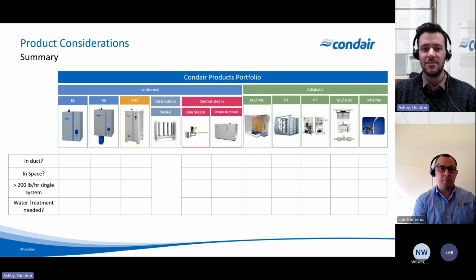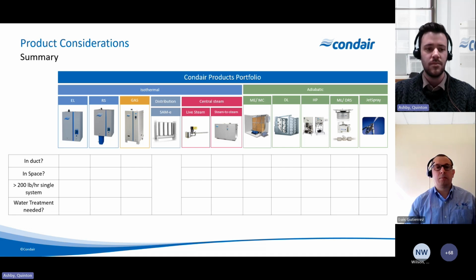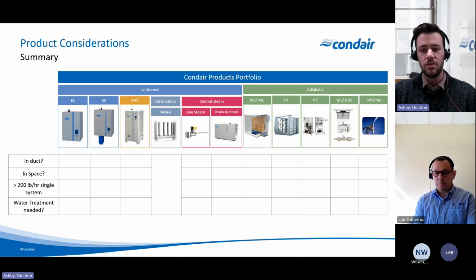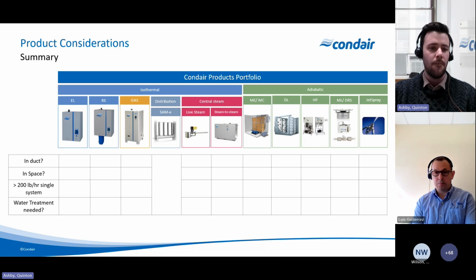So a little bit more specialized for the specific application, but then again, adiabatic does cover the full range. Another thing that we would want to look at too is the size of the system. That's a good first step if you're looking at a new job. And we think around 200 to 250 pounds is kind of the turning point for whether you're going to choose isothermal or adiabatic. So if we look at, at least for our product line, if a 200-pound or greater unit is available, if we look at electric systems, we don't offer more than 200 pounds per unit.